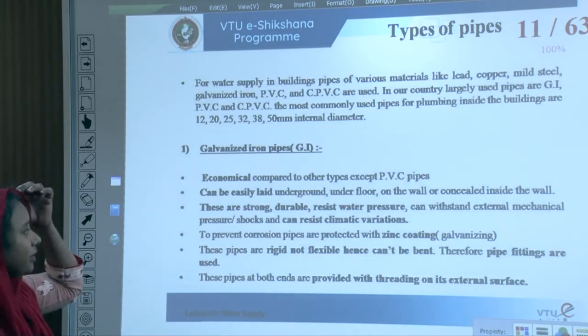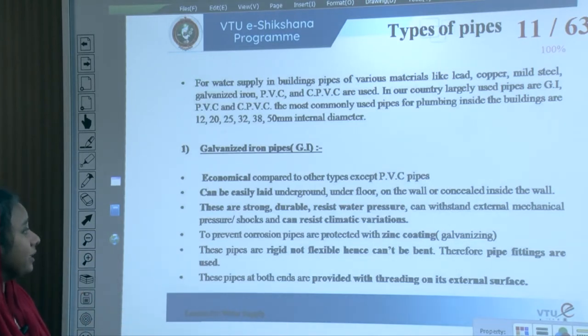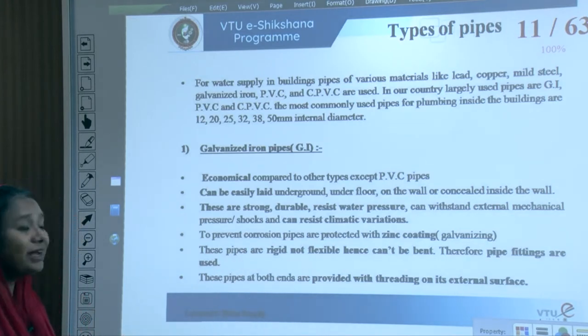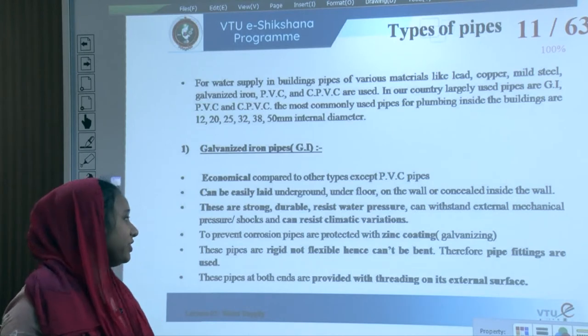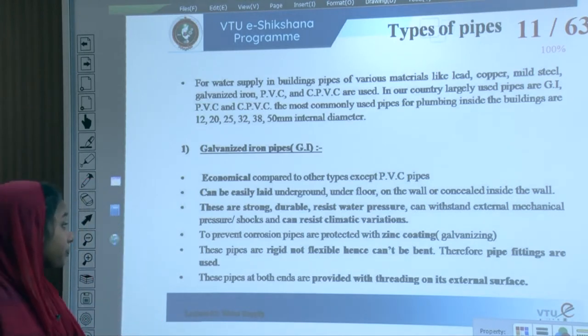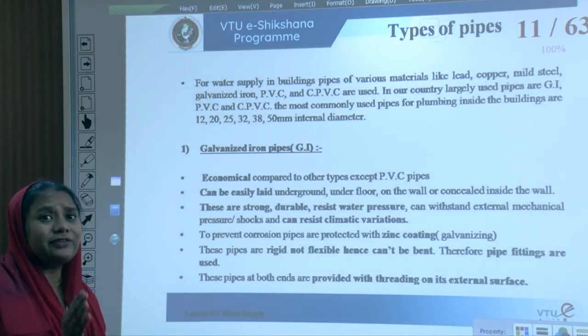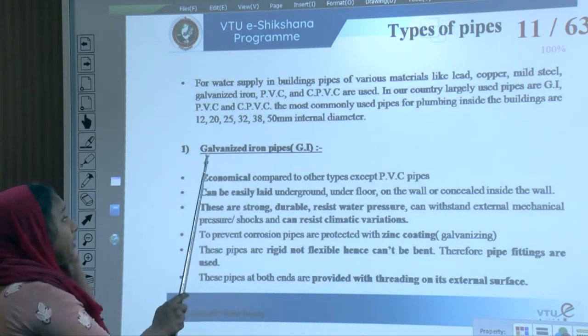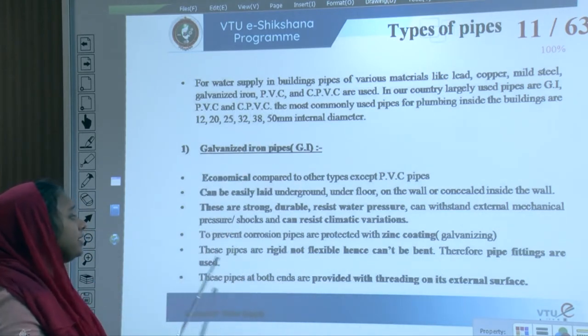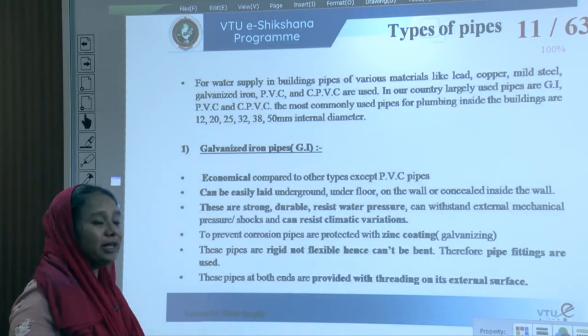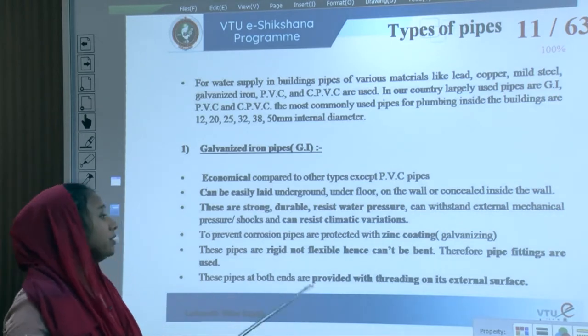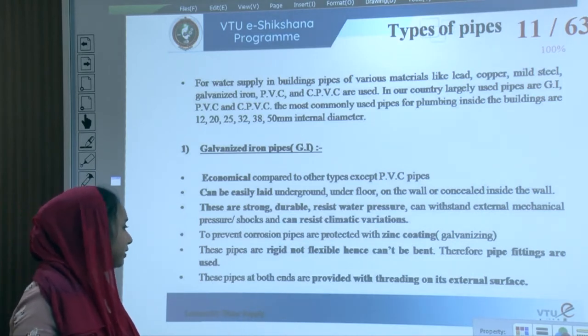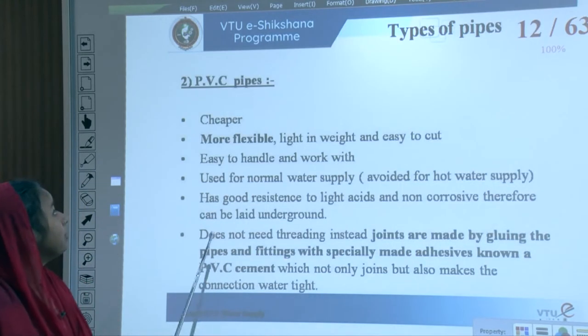Galvanized iron pipes are economical and easily laid underground. They are strong, durable, resist water pressure, and can withstand external pressure and shocks. They are protected with a zinc coating — hence the name 'galvanized iron.' These pipes are rigid and not flexible, so they cannot be bent; instead, pipe fittings with threading on external surfaces are used at both ends.